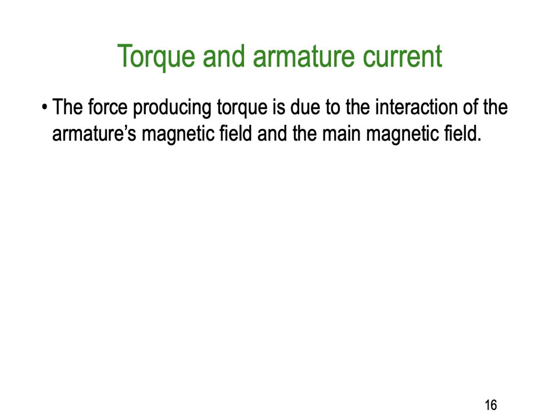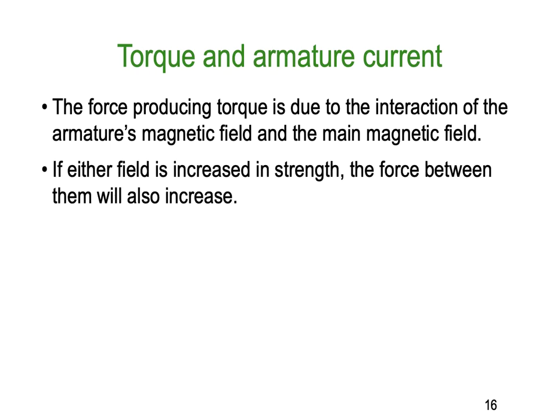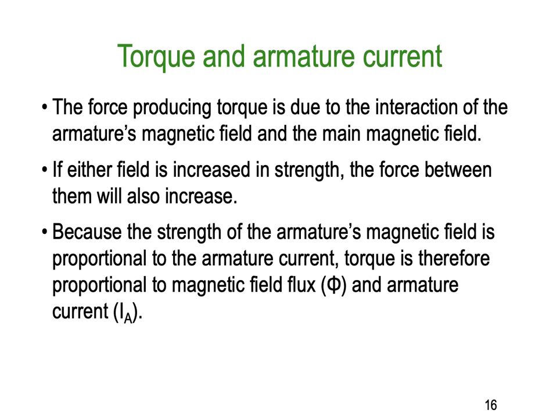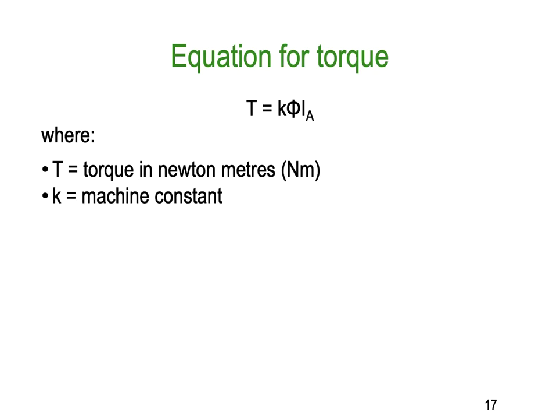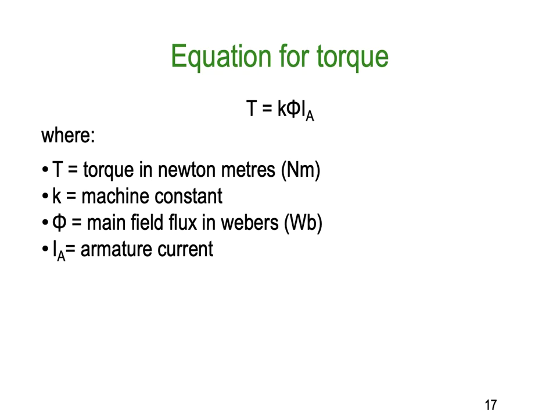Torque and armature current: the force producing torque is due to the interaction of the armature's magnetic field and the main magnetic field. If either field is increased in strength, the force between them increases, meaning the motor can carry heavier loads. Because the armature's magnetic field is proportional to the armature current, torque is proportional to flux Φ and armature current I. This gives the formula T = kΦI, where T is torque in newton metres, k is a machine constant, Φ is main field flux in webers, and I is armature current.